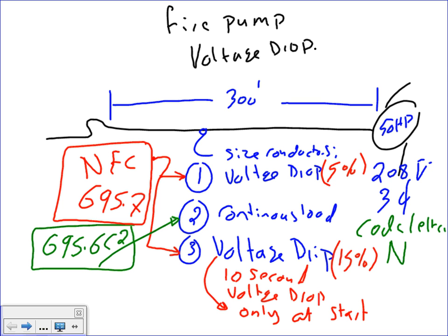Okay, we set the criteria. That's example number 1, and the only one we're going to do, probably. Any question, guys? So we're going to size 3 things and call it a quit. Everybody knows we're getting the information from the NEC code: what's a drop, what's a dip, what's continuous load. Everybody knows what continuous load is, right? 3 hours or more at full current. The voltage usually stays the same.